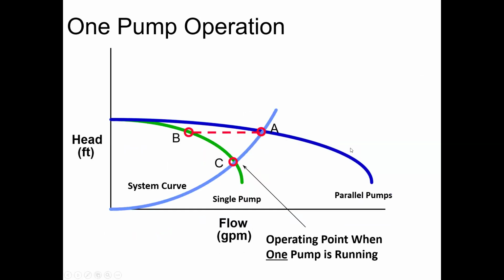What happens when only one pump's running? Where does it operate? Because sometimes the first instinct would be, hey, if I pick 2 pumps at 500 gallons a minute each, so I get my 1,000, and then one pump's off for whatever reason, it's not working, someone intentionally shut it off, loads light, I'm going back to the 500 gallons a minute. But I can't, because the pipe size is there for 1,000 gallons a minute. So I don't have the resistance to stay at 500 at that head loss. So I'm going to operate further out to the right of that curve, and I'm going to intersect the system curve of that 1,000 gallons a minute at whatever that head loss was when both pumps are running. So in this case here, it's saying, hey, I'm going to intersect at point C for single pump operation, which sometimes can be beneficial because the percentage isn't 50%. It could be 70, 75, 80% with single pump operation. So it's something to be aware of.